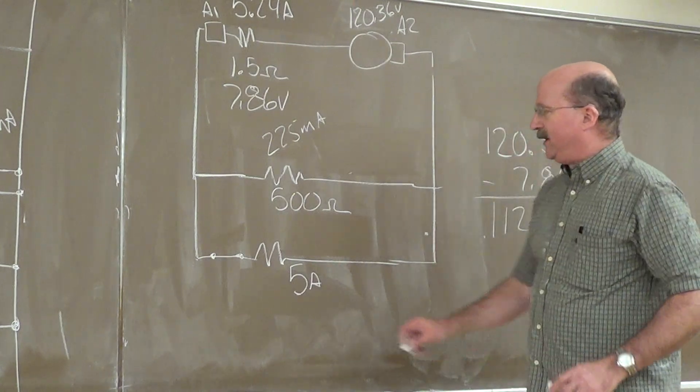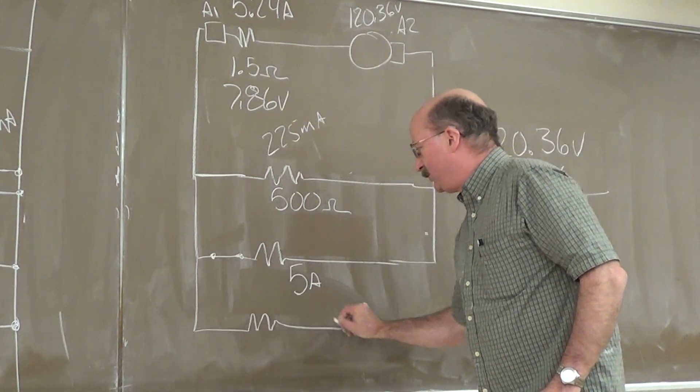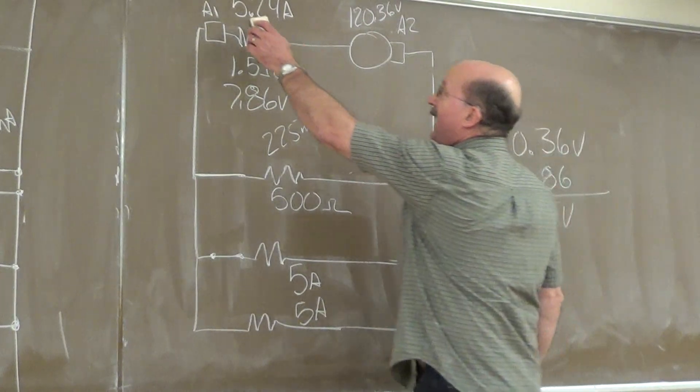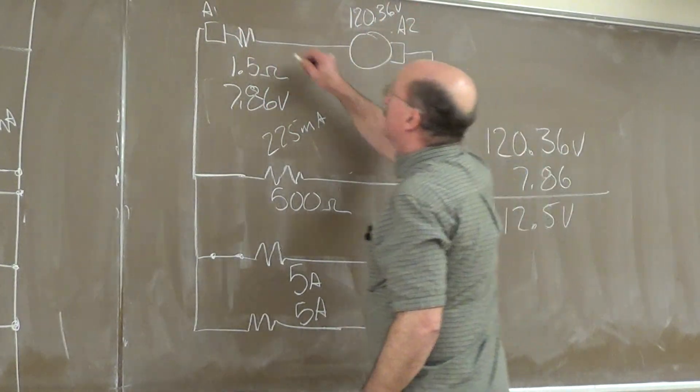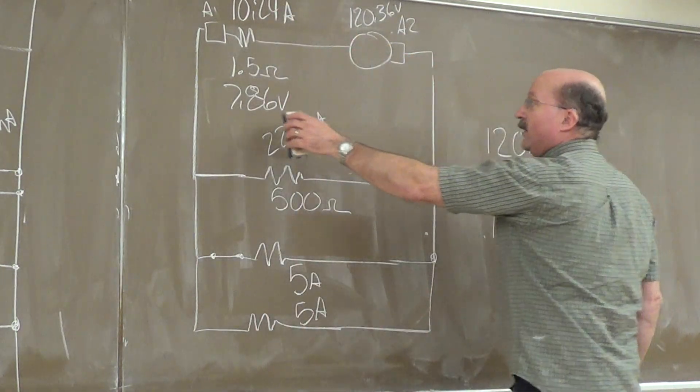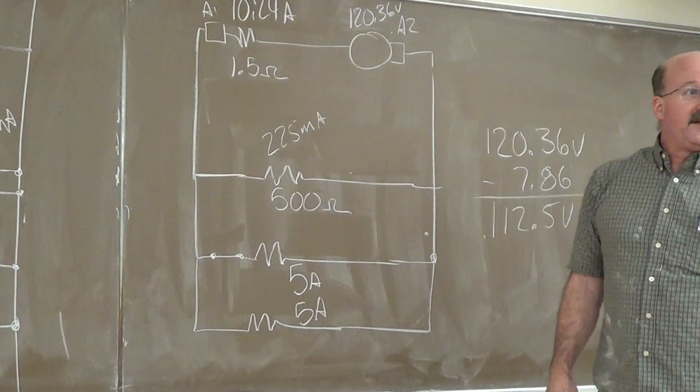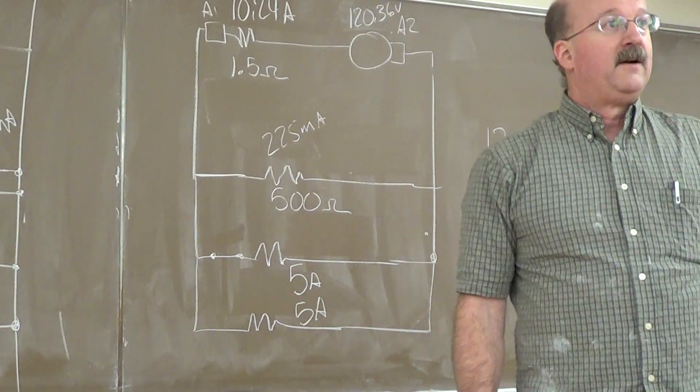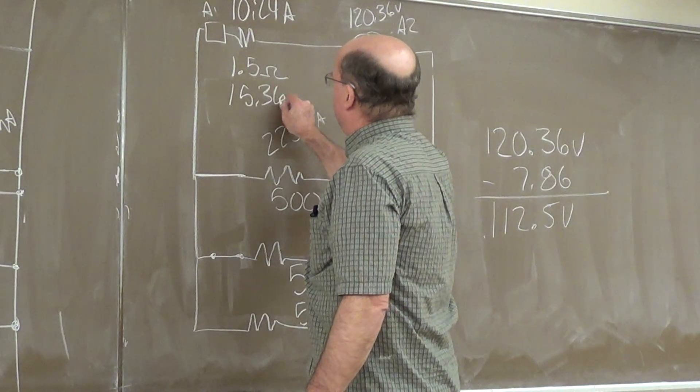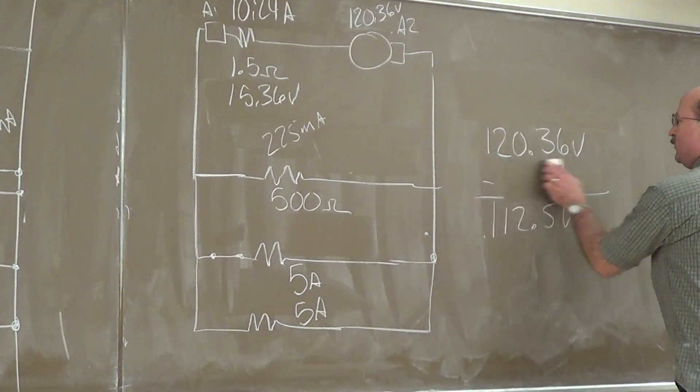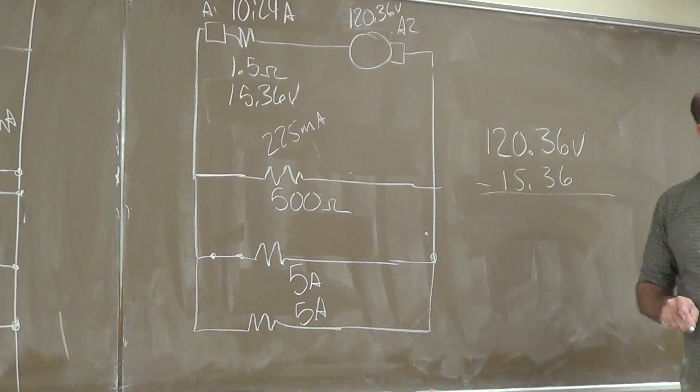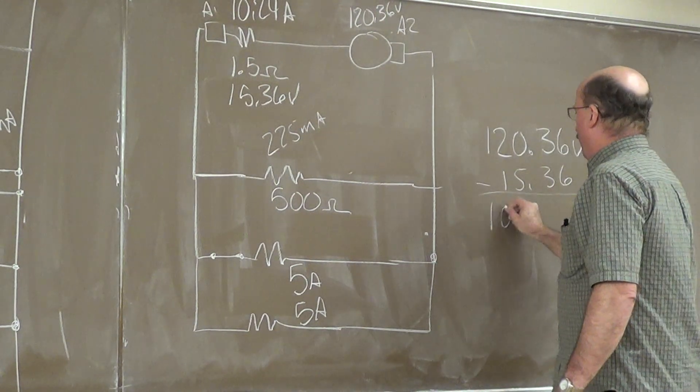But look at this very simply. If we come over here, now we increase this to another 5 amps here. Where are we at here? 10.24. 10.24 amps. 10.24 times 1.5 gets us how many volts? 15.36. 15.36. 120.36 minus 15.36. Oh, that's nice, isn't it? 105 volts.